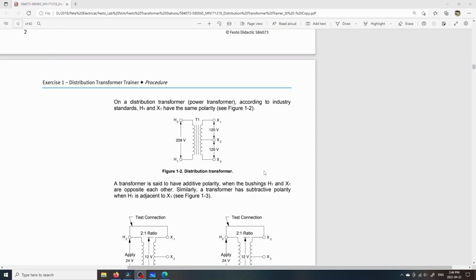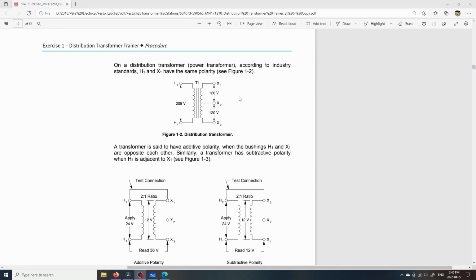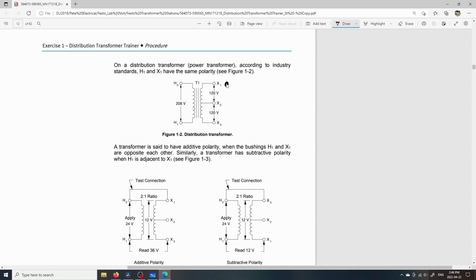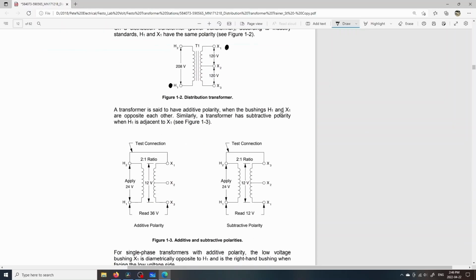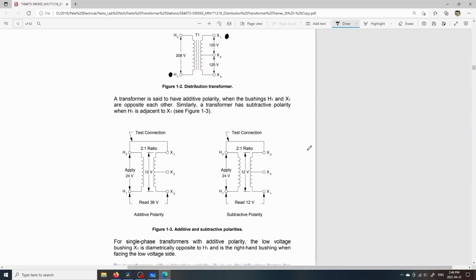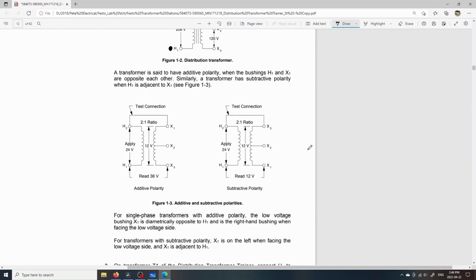On the distribution transformer, according to industry standards, H1 and X1 have the same polarity. I usually note that with dots on each one to denote their polarity. A transformer has additive polarity when bushings H1 and X1 are opposite each other, and subtractive polarity when H1 is adjacent to X1.